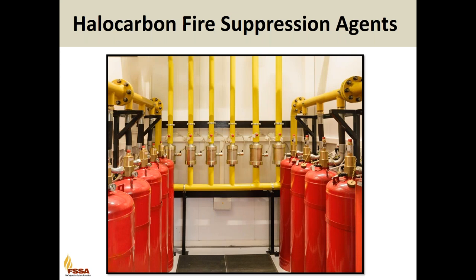The first category is the halocarbon clean agents. This group of suppression agents is the most comparable to halon in several ways. They have similar characteristics to halon in the way they are stored and delivered and the applications in which they are used. They primarily extinguish fire by absorbing the heat from the flame.